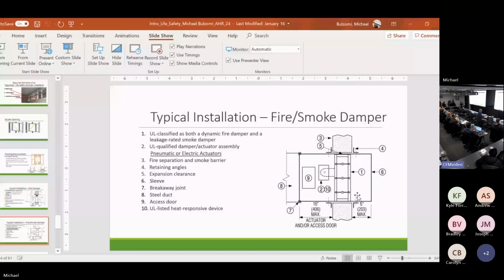What's the minimum the sleeve can extend out of the partition? UL and NFPA does not regulate that. They don't care. The minimum is whatever is needed for a proper UL qualified installation. So on a fire damper, I might ship a standard 16-inch sleeve. That's a lot of sleeve that you don't need for a fire damper.